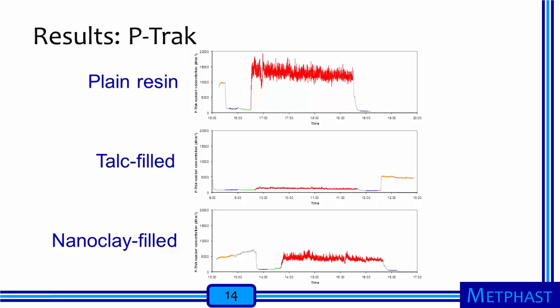The figures are color-coded. The orange data represent the particle concentrations in the room during a period when the enclosure door was open and we pulled room air directly into the apparatus using the fan unit. The blue data are background concentrations after we shut the enclosure door and air entered the apparatus through the HEPA filter. The green data are the background concentrations when the enclosure door was shut and the granulator was turned on with no test plaques being shredded. We will primarily look at the red data, which were taken over 2 hours when the test plaques were being shredded.